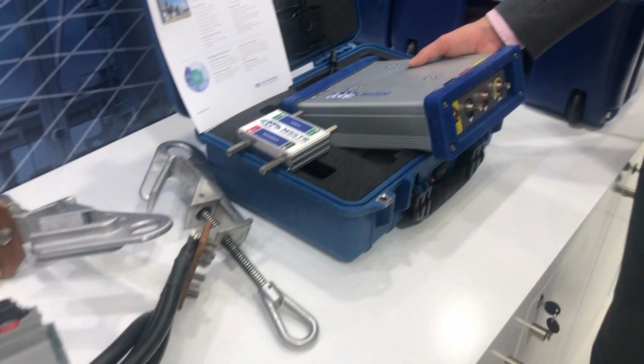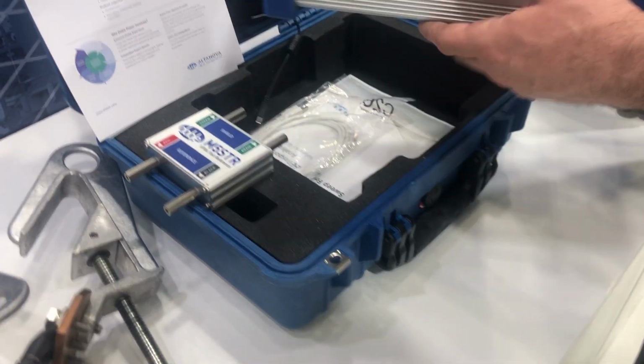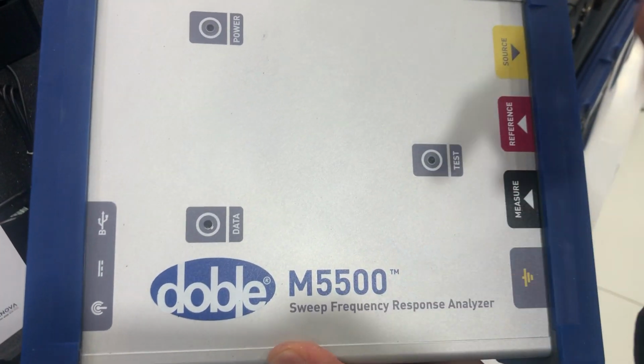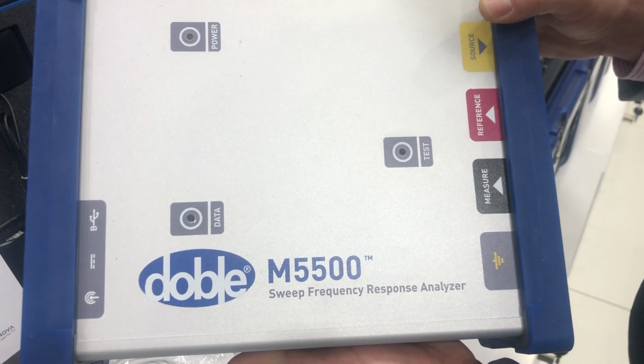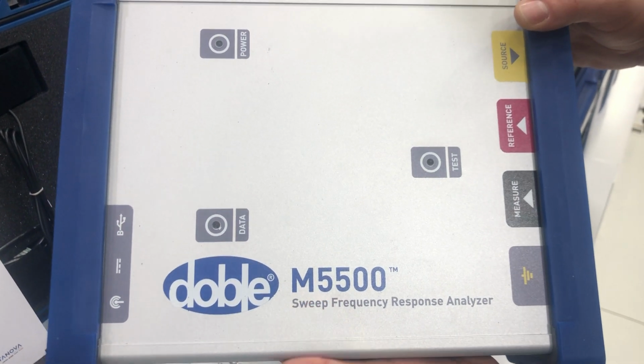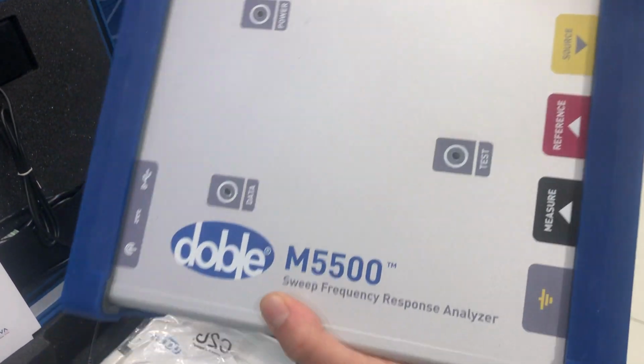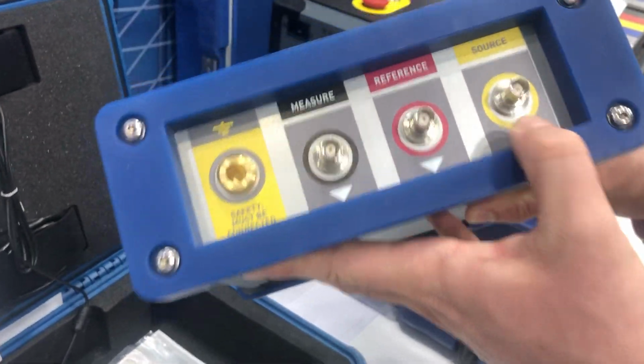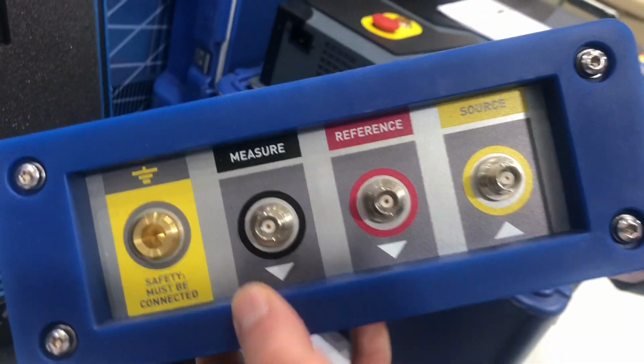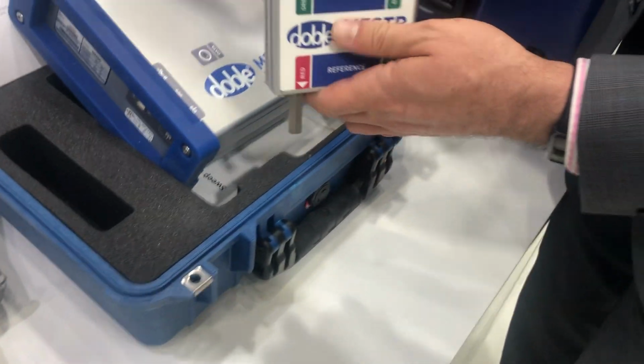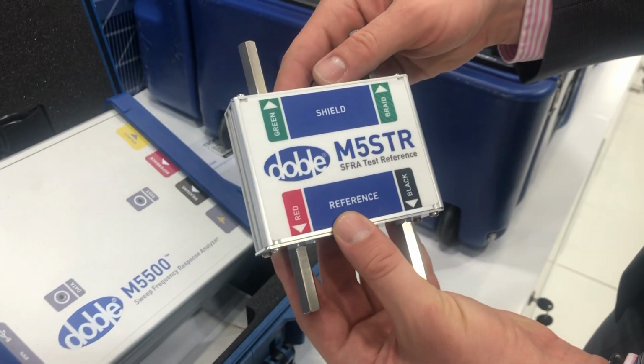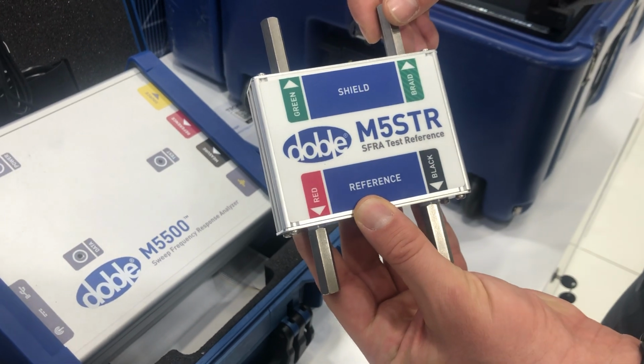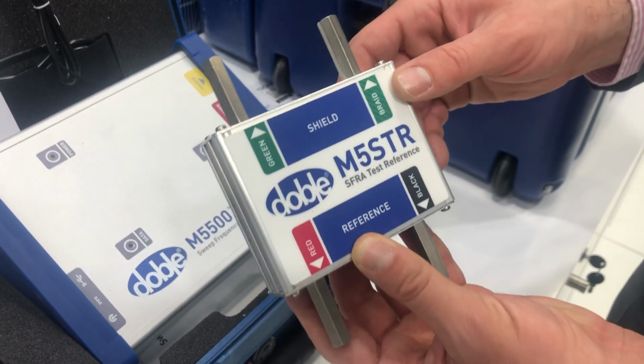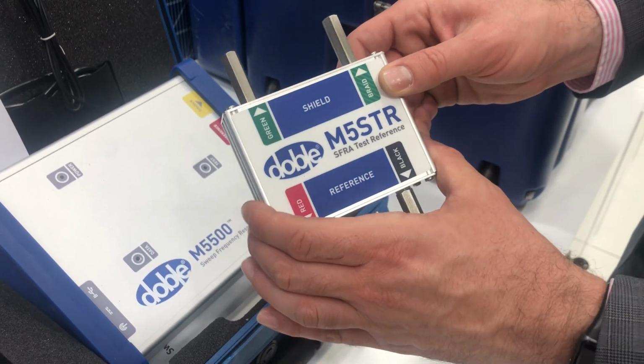Now let's show some Doble devices. So this is an industry standard Doble M5500, a sweep frequency response analyzer with the frequency from 10 Hz to 25 MHz. Here you have the source, the reference and the measure, which is very nice. With the device you also get this reference bridge where you can basically get the response which is always known, and thus compare, understand if the device is calibrated or not.